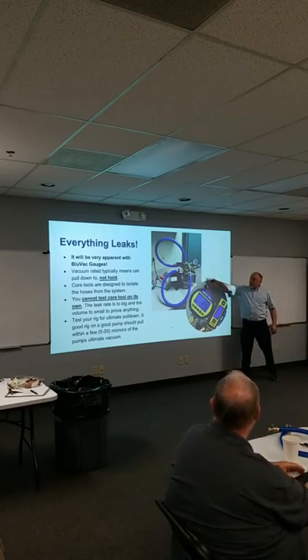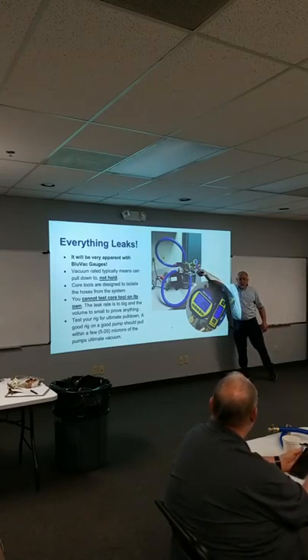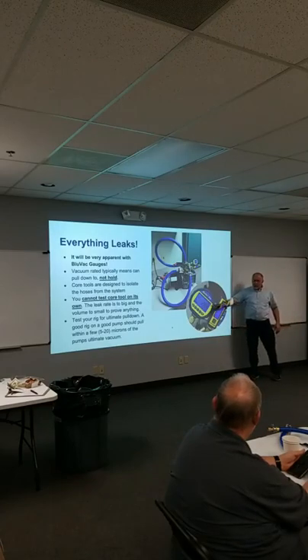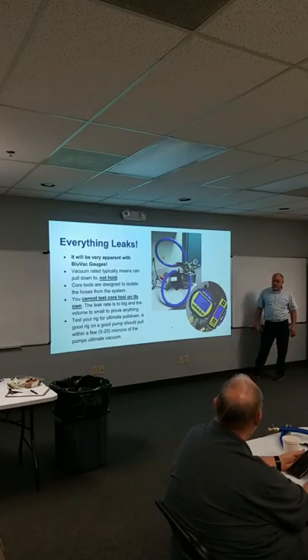Well, first of all, why is there a pressure difference? Because there's always a pressure difference. It's higher pressure at the far end of the hose than it is next to the pump, otherwise pressure wouldn't flow. It's gotta go from high to low, right? And while this is running, eventually these two will converge. It'll get closer and closer, but this is gonna take hours, okay? This was probably running that pump for an hour before it got down to this 20 micron level, right?